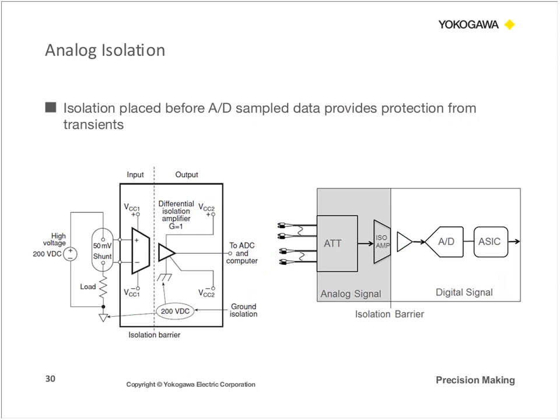So let's talk about one of the oldest technologies out there. A common type of galvanic isolation used in early designs was the analog isolation amplifier, and it was used to isolate the sensor circuit on the factory floor from the signal processing system in the control room. And isolation amplifiers also protect the data acquisition components from potentially destructive voltage present at remote sensor systems. So these isolation amplifiers are incredibly useful if you also need to amplify low-level signal changes in a multi-channel application.